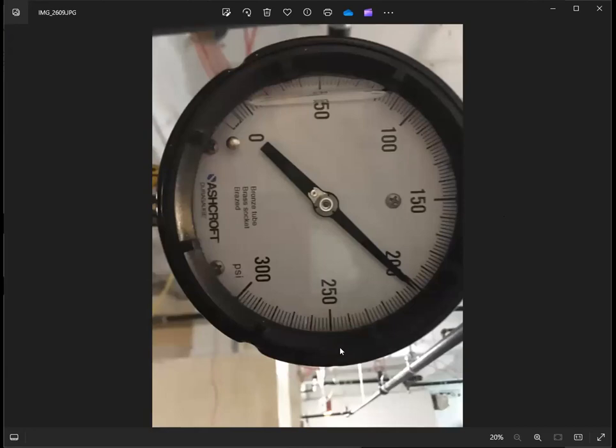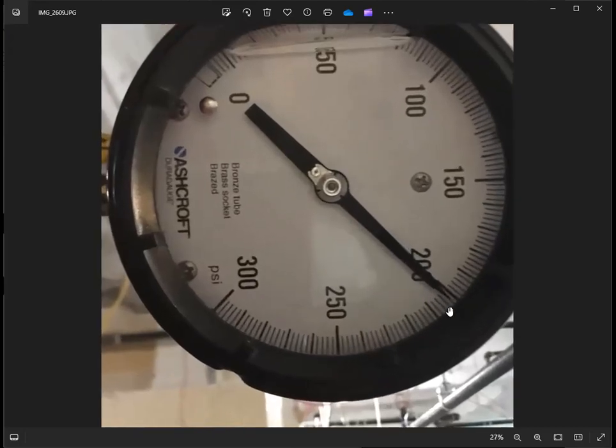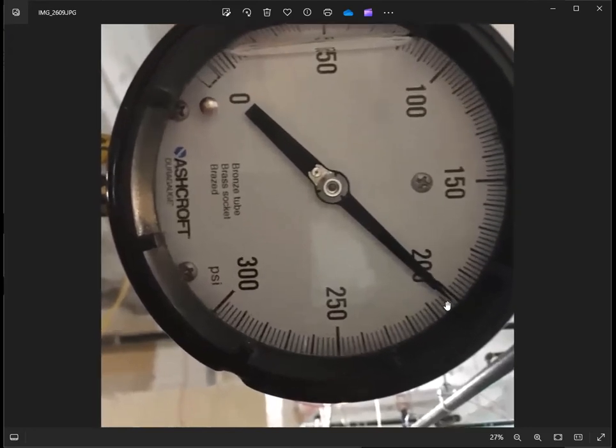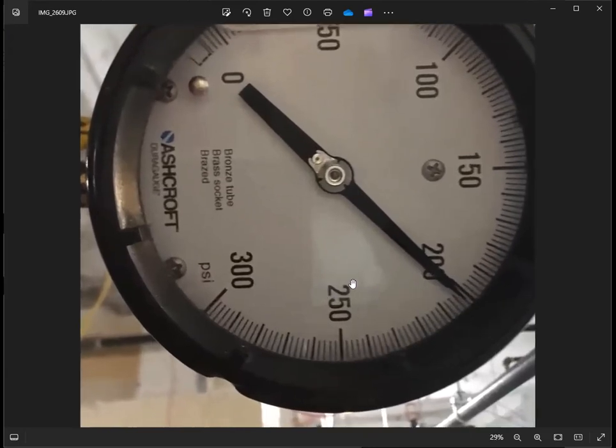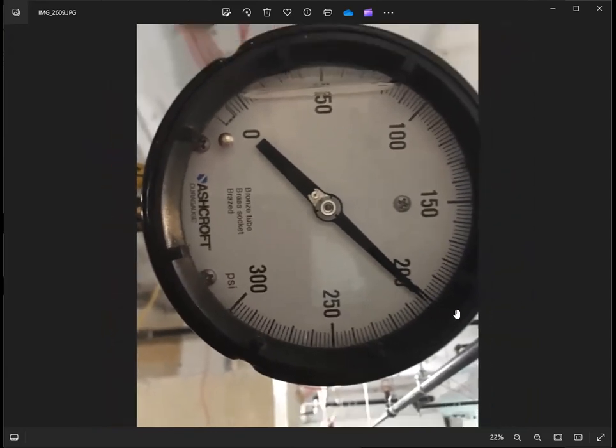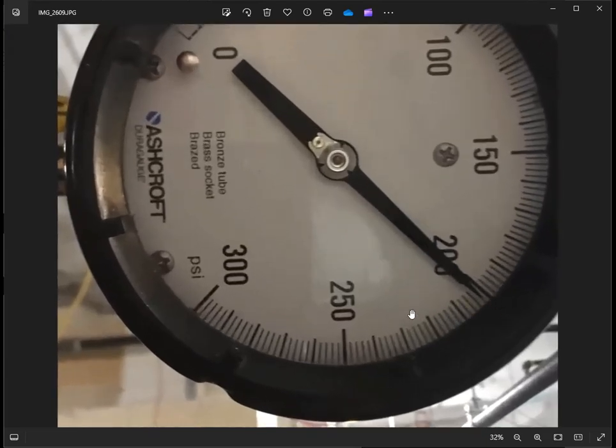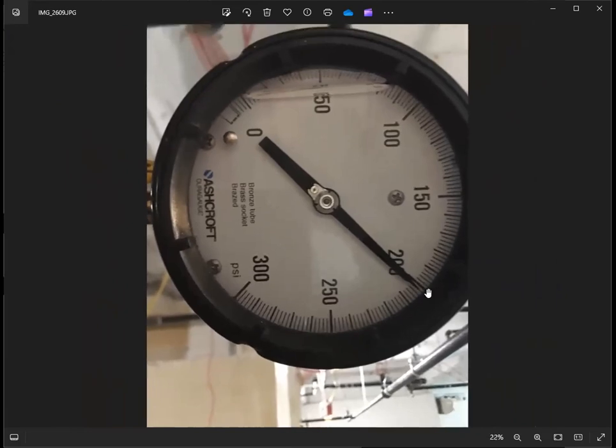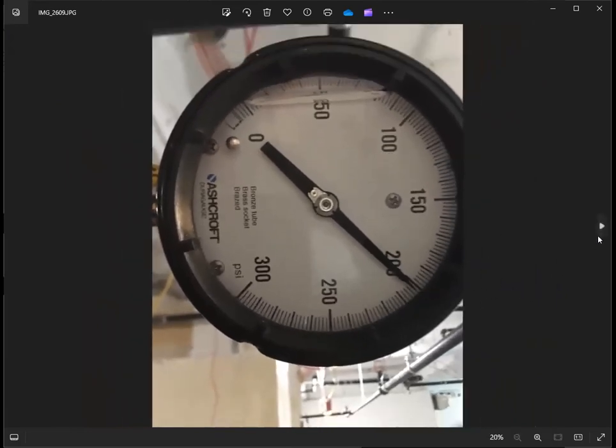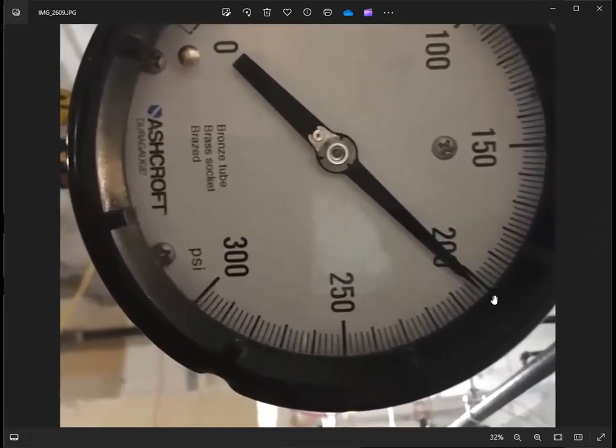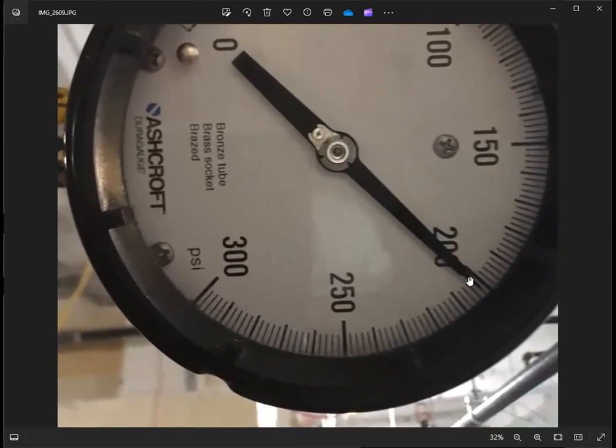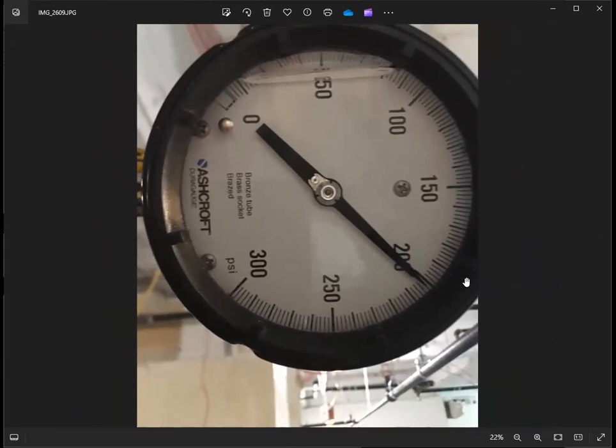So take a photo closely of the dial, the hand of the pressure. The requirement is 200 or beyond 200 psi, pounds per square inch pressure. So the requirement is 200 for a 2-hour test. Take note and mark this dial. This hand should be like one line over the 200 psi increment of this pressure gauge. So within 2 hours, it should not move at all. It should not drop to 200 from the very time that you take the photo.